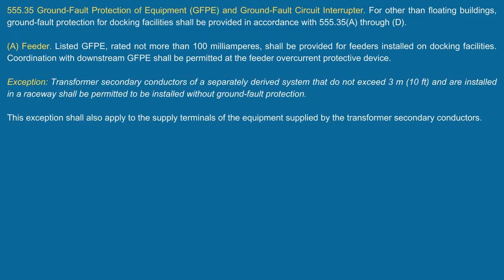So if you look at A is where we deal with a feeder, and it says listed ground fault protection of equipment rated not more than 100 milliamperes shall be provided for feeders installed on docking facilities. Coordination with downstream GFPE shall be permitted at the feeder overcurrent protection device. Okay, now, first of all, unlike what he said before, he says a feeder, like if I was going over and hitting a fusible type disconnect, and then I go to a single motor, he says that's a feeder. That's not correct either. A feeder, I've already showed that, is where you go to two or more items.